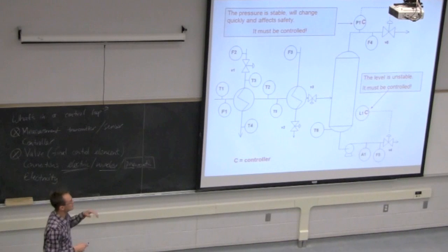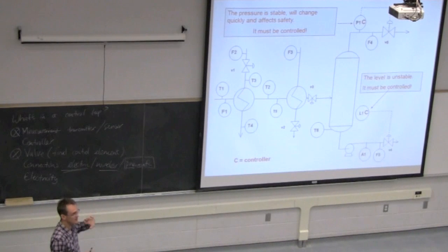Yeah. So we're going to see mechanisms later where we can relieve pressure should it build up. But in a situation where there's loss of that power, let's say the operator just breaks that single line on its own, we want that valve to fail in a position which causes the least amount of damage to us and the environment. And that's in the open position, so it can keep moving out and not leave a pressurized state here in this vessel.